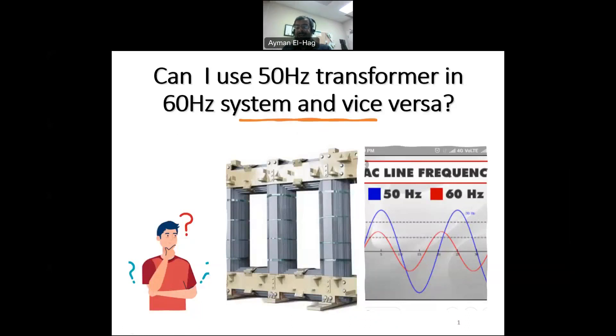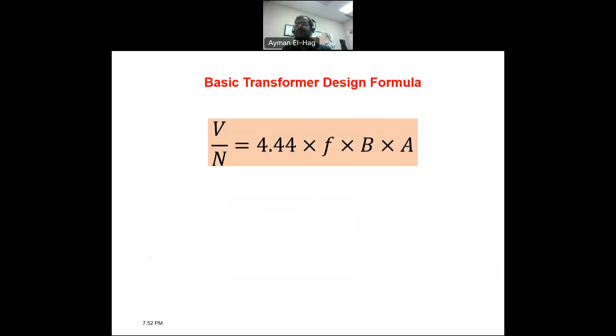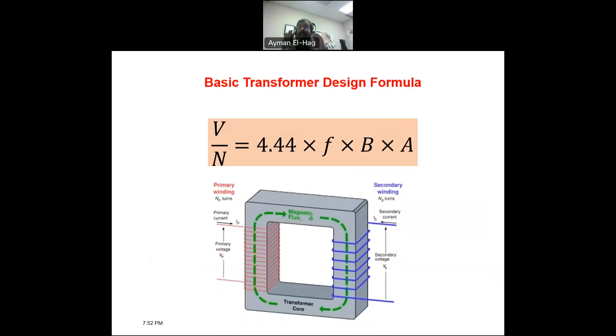The question is, if I design a transformer to work in a 50 hertz system, can I use it in a 60 hertz system and vice versa? And to answer this question, we need to start from the fundamental, the basic transformer design formula, which is the voltage per turn is equal to 4.44 times the frequency times B, the flux density times A, the cross-section area of the core. So, let's first understand this formula, and then let's try to understand from where it comes, how we derive this formula, and then use that formula to basically answer the question.